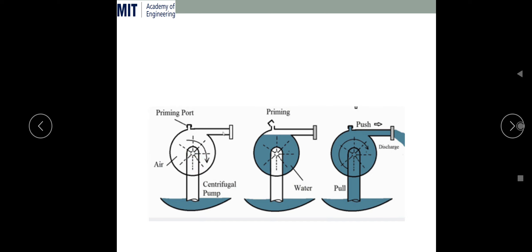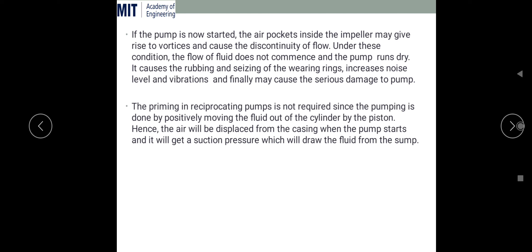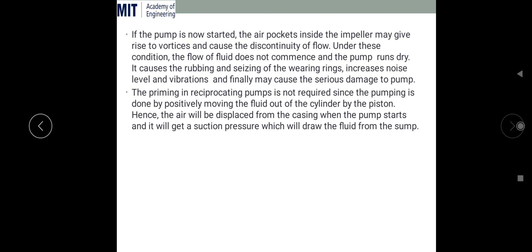The pump cannot generate enough pressure with air inside. So the main function of priming is to remove the air from the casing to create suction pressure — a pressure below atmospheric, near vacuum. We fill the casing, suction pipe, and delivery pipe using external water so all air is removed. Once the impeller starts rotating, there is water everywhere, sufficient suction pressure is created, and water flows continuously from the sump through the casing to the delivery point. This is the purpose of priming in a centrifugal pump.